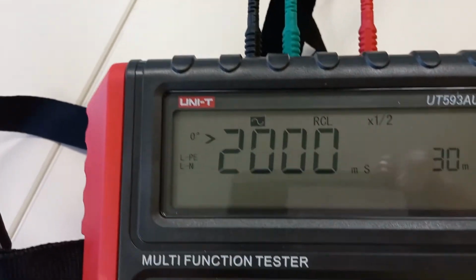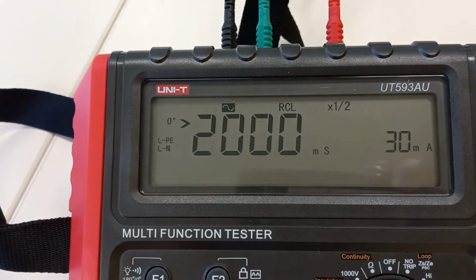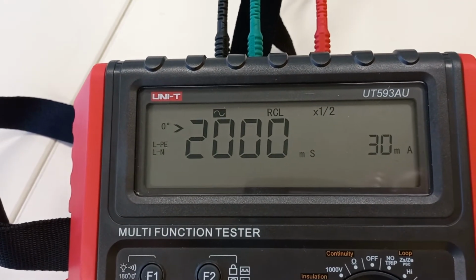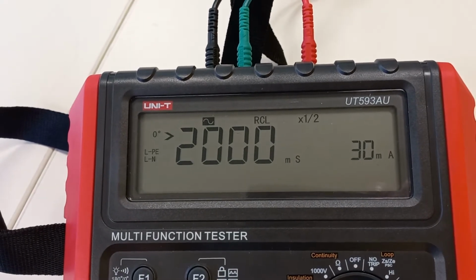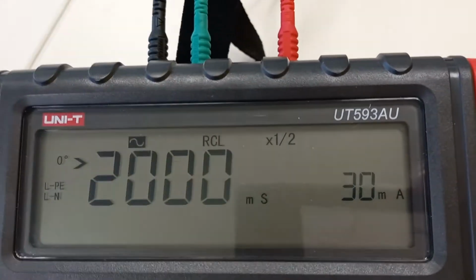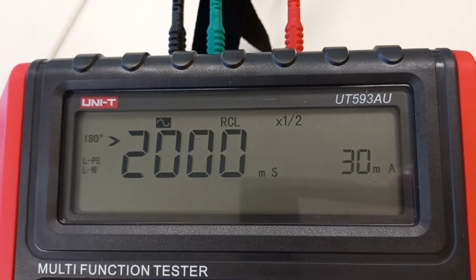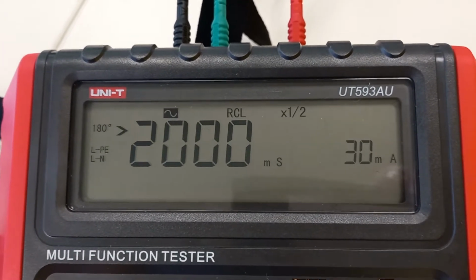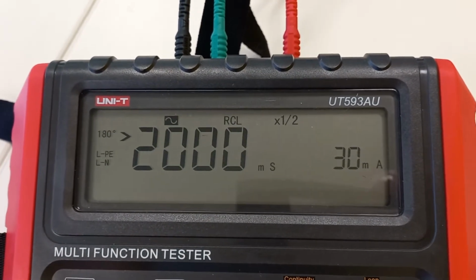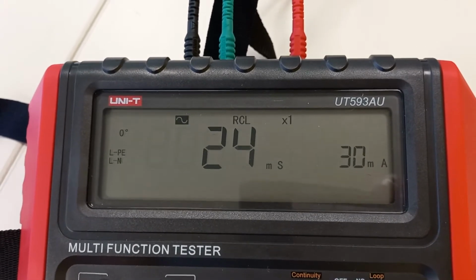It timed out at greater than 2000 milliseconds at 0 degrees, which is excellent. It didn't trip. That's at half the rated current. At 180 degrees, it also timed out at half the rated current and did not trip.